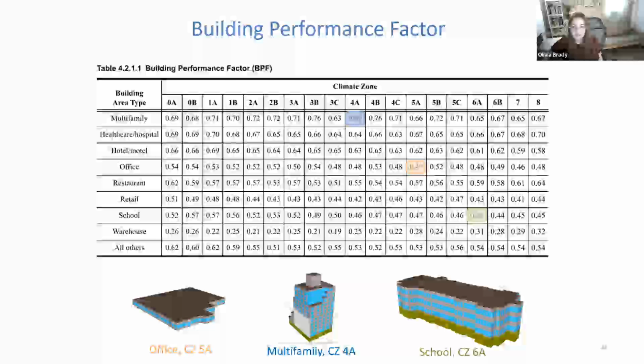For example, an office building located in climate zone 5A has a building performance factor of 0.49. A multifamily project in climate zone 4A has a BPF of 0.69, and a school located in climate zone 6A has a BPF of 0.46. Those are the building performance factors used in that PCI target equation, and these values represent the general change in stringency for these climate zones and building types.